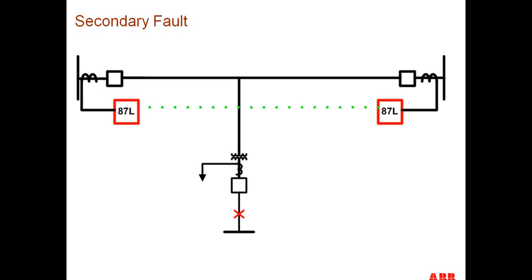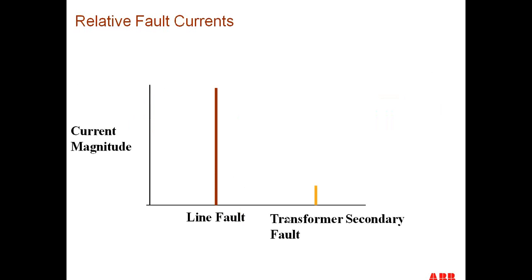We use that information in our relays and devise a method to distinguish between a high side fault and a low side fault, because we know that a line fault will be one magnitude of current, and our transformer secondary fault will be a much smaller magnitude of current. We can use a level detector: any current above this will be considered a line fault, and we would operate instantaneously. Any current below this would be a transformer secondary fault, and we can time delay the operation of our line current differential relay to let the overcurrent relay on the secondary of the transformer operate first.